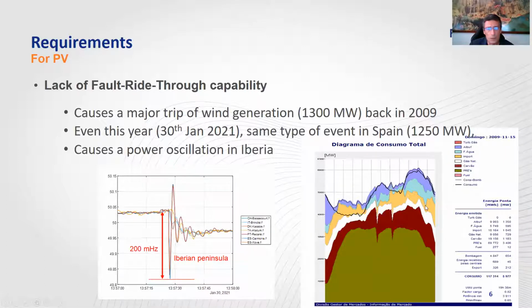These are the biggest events that we had back in 2009, when the issue was still in wind, okay? PV in Portugal is still in small sizes compared with the wind penetration. But at that time, back in 2009, we had 2 faults, and we lost like 1,300 megawatts of wind, which is bigger than one nuclear power plant in Spain. So this was a big surprise. But anyway, even this year, on the 30th of January 2021, we had a similar event in Spain, and we tripped, and we lost also almost the same amount of power.